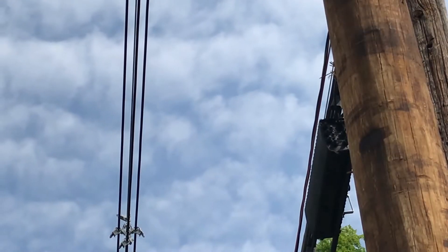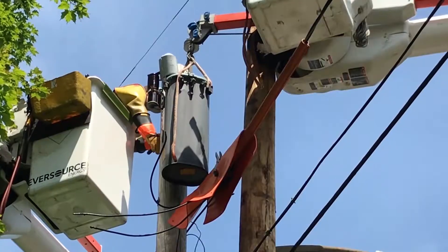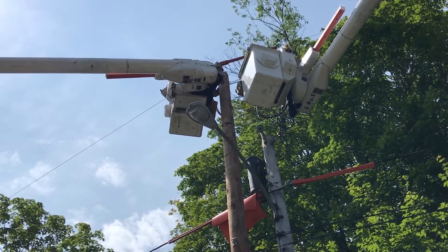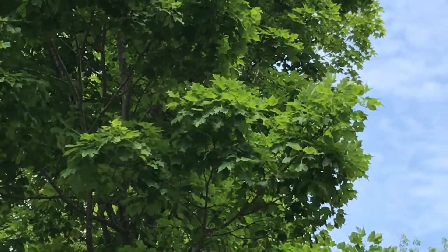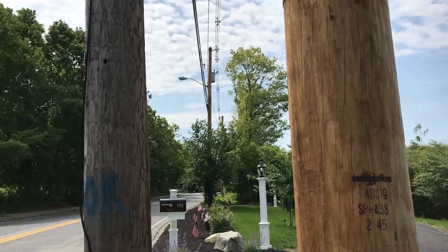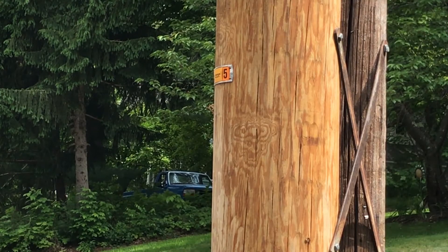More than a mile and a half of bare power lines have been replaced with new insulated cables. It's also a larger wire — the older wire was thinner, so this new wire can carry more load. Now there's a tree covering and it's an insulated wire, so if a branch does come in contact with it, it's less likely to cause a power outage. We also worked closely with Verizon to replace nearly 70 utility poles.